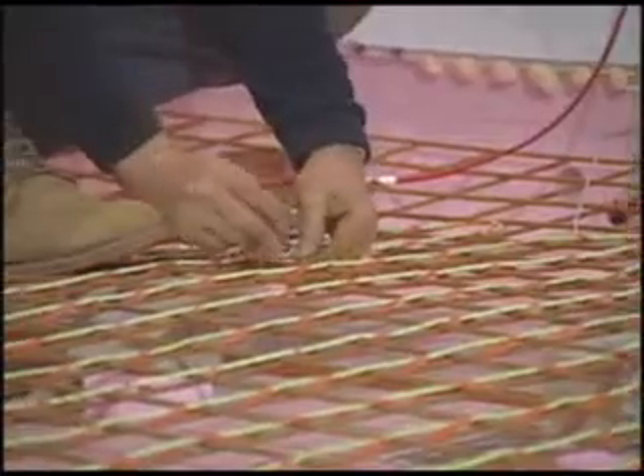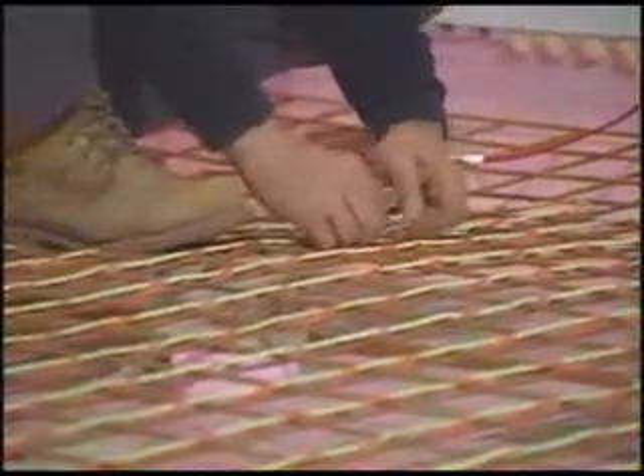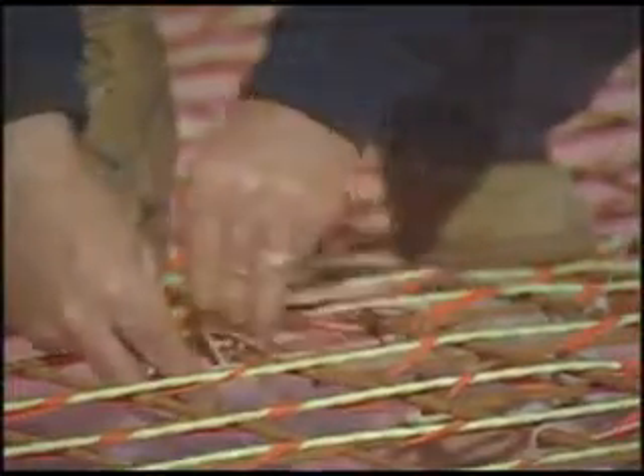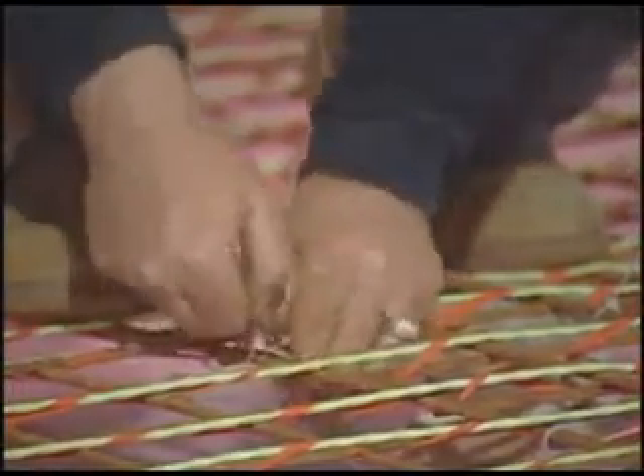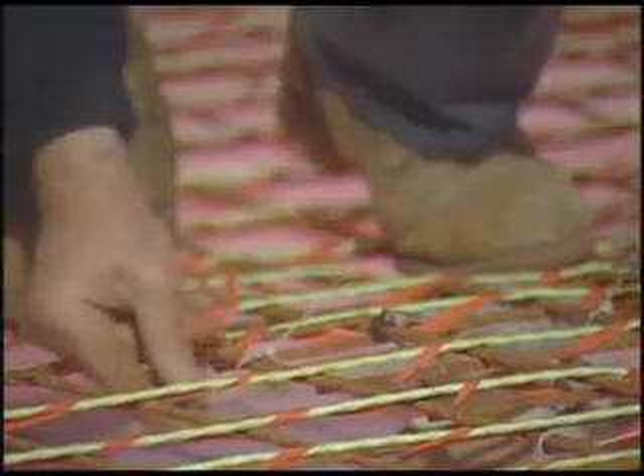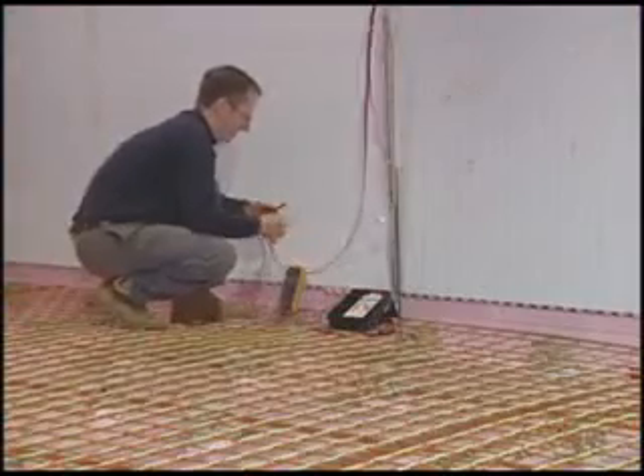Attach the sleeve to the cable conduit which already contains the cold lead. Then secure the remaining part to the mesh, making sure there is no overlap with the heating cable. Ensure that the part of the probe that will be covered with concrete is in the protective sleeve. The probe must be at least 2 feet into the heated area and exactly between two cable runs. Place it in a neutral area far from any source of heat or cold.